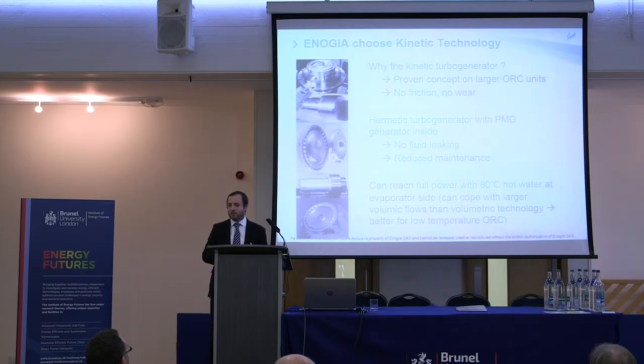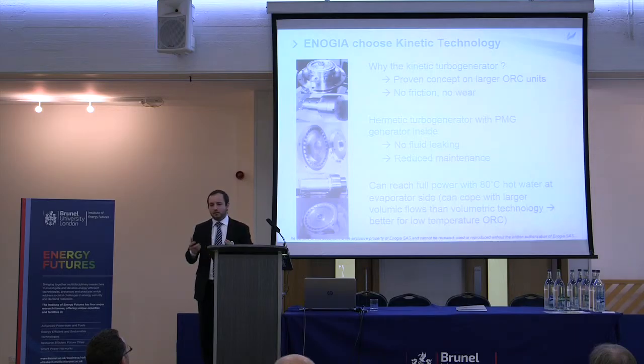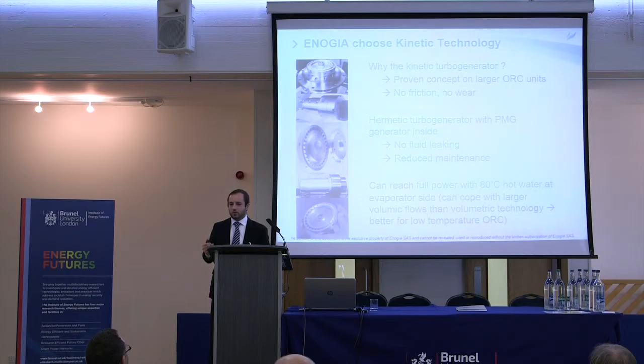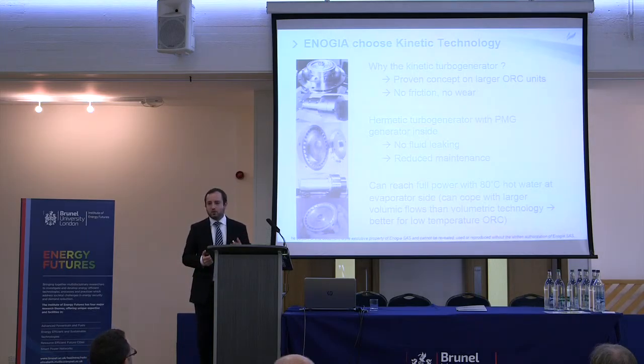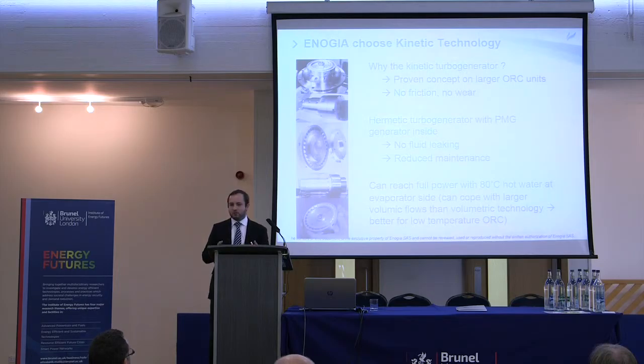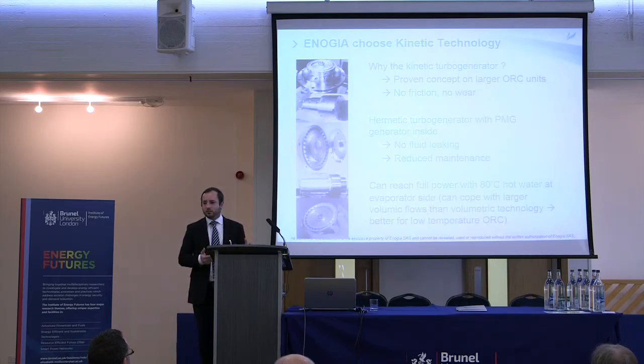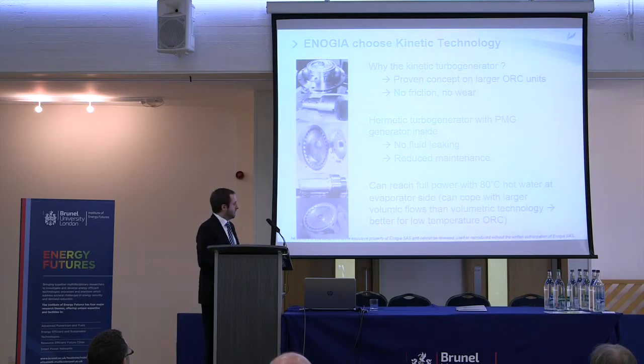This is in an ORC situation with 80 degrees centigrade hot water inlet running in a loop. I'm not speaking of things like the TFC, where you recover all thermal energy out of a cooling water source down to 30 degrees. I'm speaking more of cooling loops running in a closed loop from 80 to 70 degrees centigrade, like an engine loop. So it's very complementary technology.